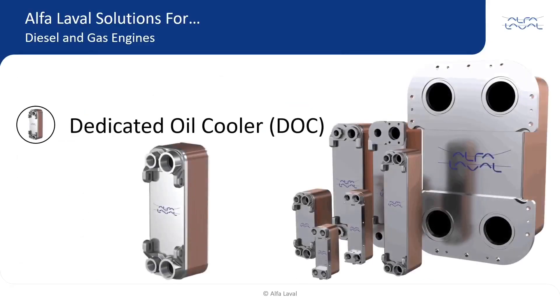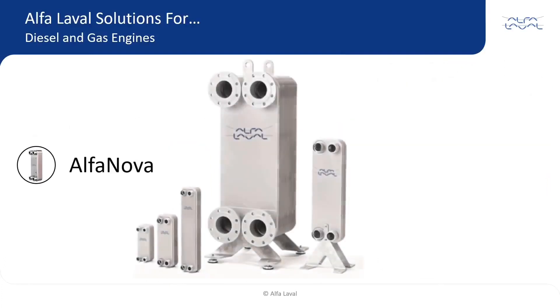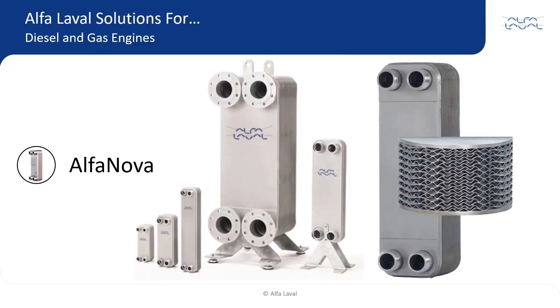DOCs use the same production concept as BHEs, but include more robust connections for rugged environments. Alfa Laval's latest version utilizes less material and, in some models, includes the added benefit of mounting holes near the ports. The AlfaNova uses similar stainless steel plates as the BHEs or DOCs, but instead of copper, a fusion bonding process is used to yield a 100% stainless steel solution. AlfaNovas are ideal for higher pressures or temperatures, or for fluids not compatible with copper.